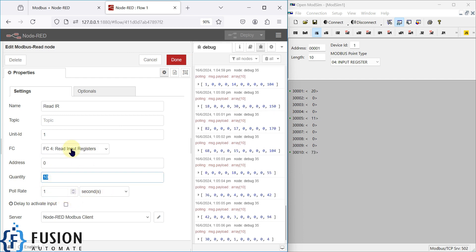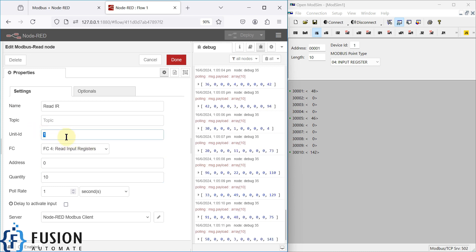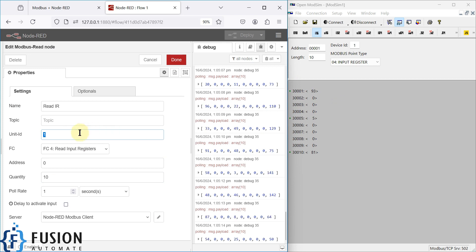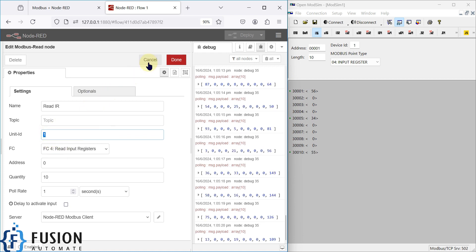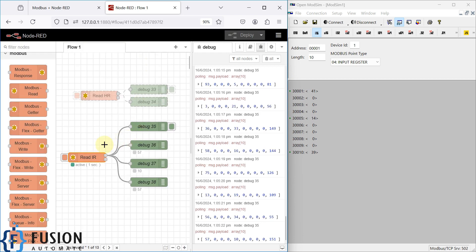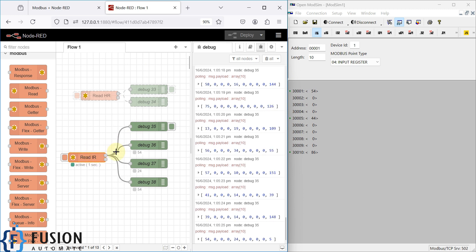This is how you can use Node-RED to read the input register data of any Modbus TCP device. You can specify the starting address, the quantity, the poll rate, and what type of data to read — in this case, input register. You can also specify the unit ID, which is useful if you have multiple devices with different unit IDs, so it will only read data from that specific device.